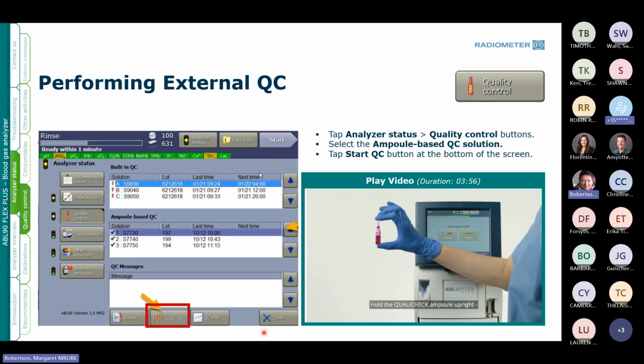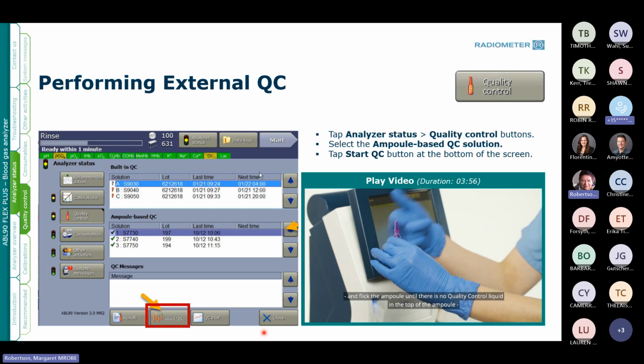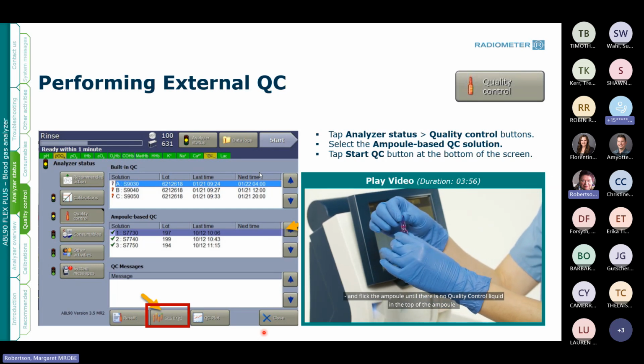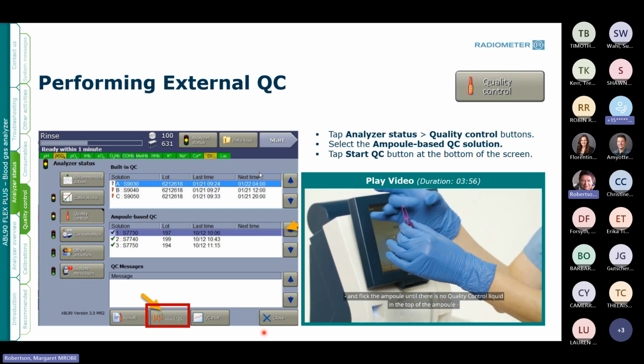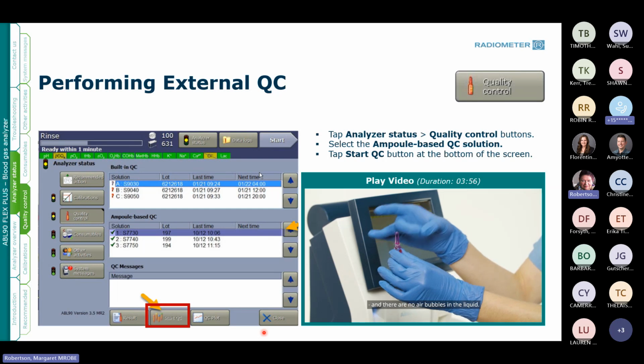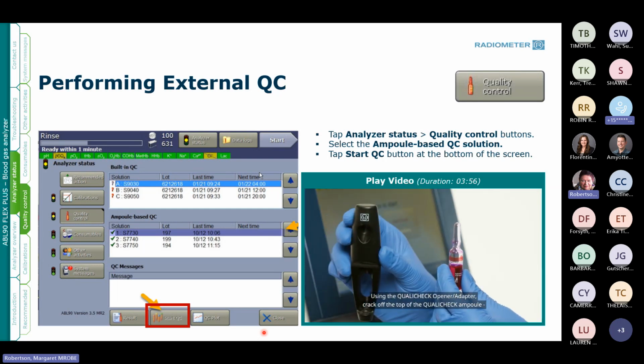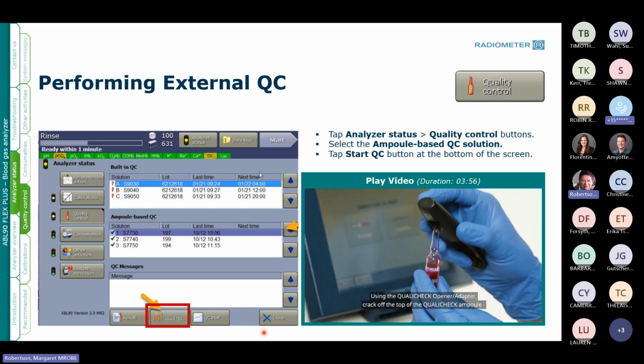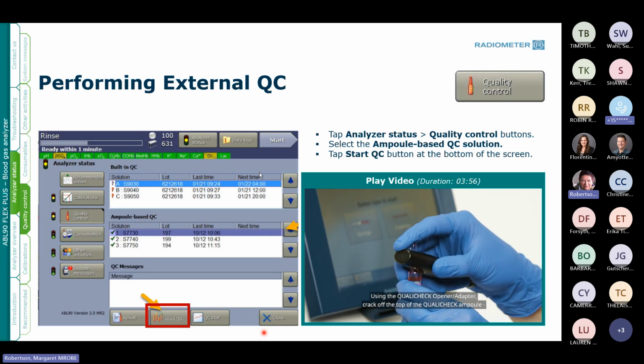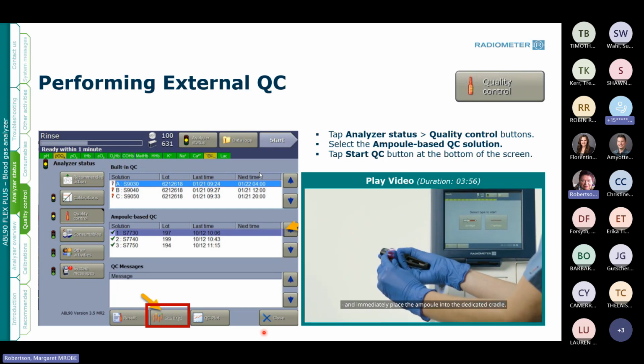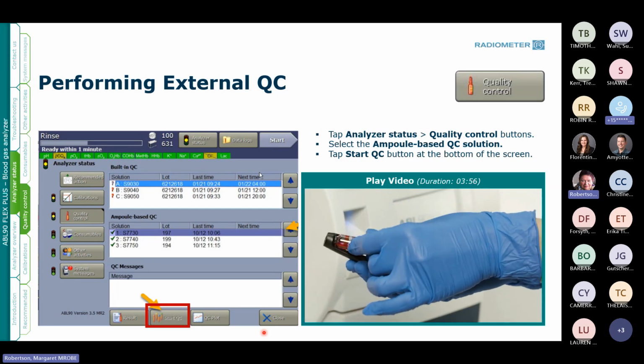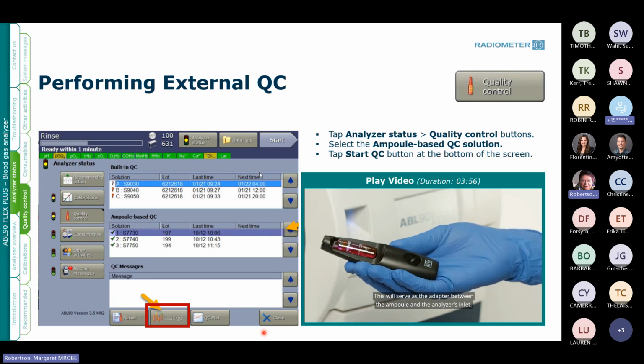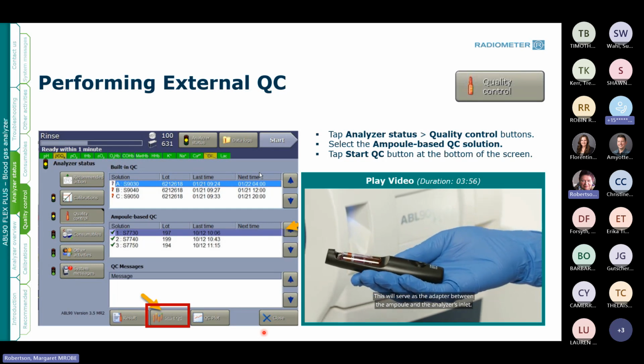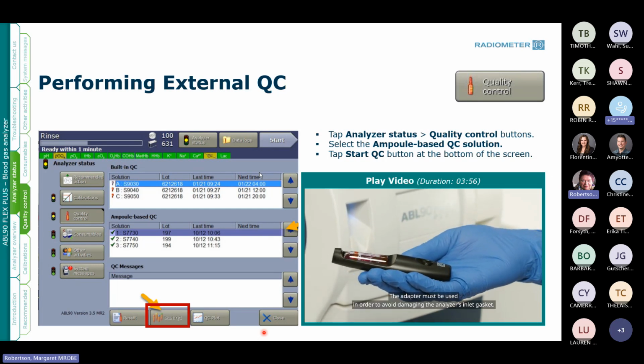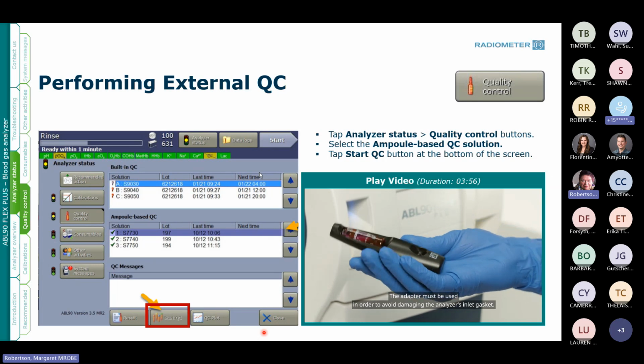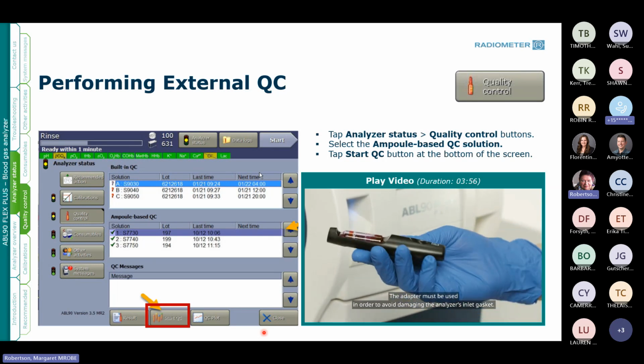Hold the QualiCheck ampoule upright and flick the ampoule until there is no quality control liquid in the top of the ampoule and there are no air bubbles in the liquid. Using the QualiCheck opener adapter, crack off the top of the QualiCheck ampoule and immediately place the ampoule into the dedicated cradle. This will serve as the adapter between the ampoule and the analyzer's inlet. The adapter must be used in order to avoid damaging the analyzer's inlet gasket.